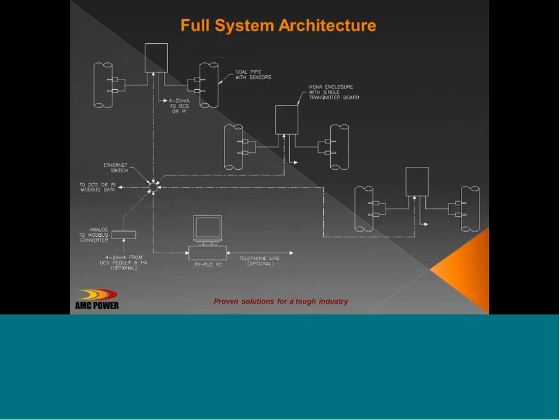Typically, the transmitters could be located separately along the burner deck or anywhere in the plant, and then the 4 to 20 sent back to the DCS. Or if the digital signal is used, all the transmitters can be daisy chained together, and then a home run Cat5 cable can be run back to the control room.